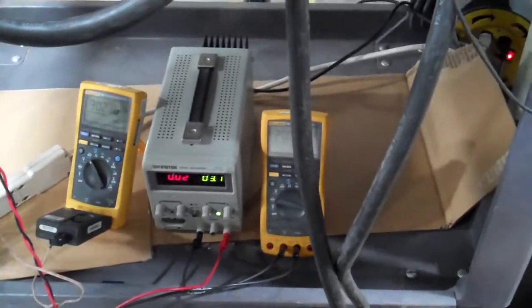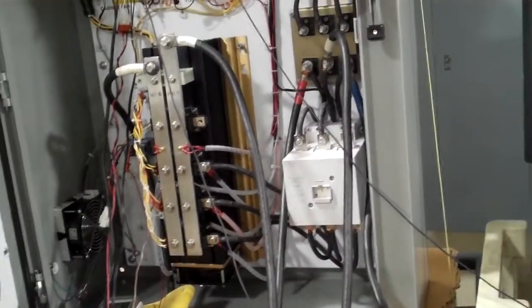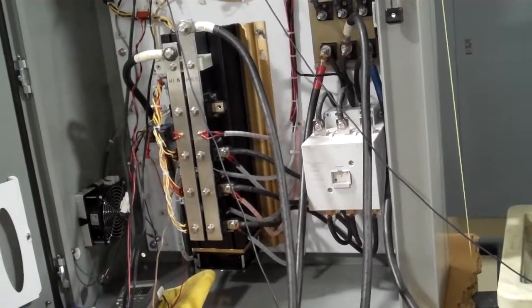So again, this was done for a maximum of 260 amps DC, and we verified that the fan came in. Once the fan came in, it reached a thermal equilibrium, and it looks pretty safe.